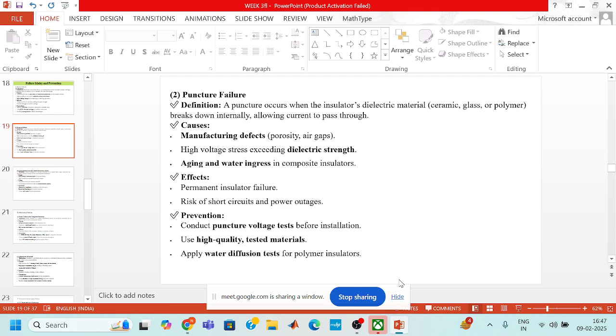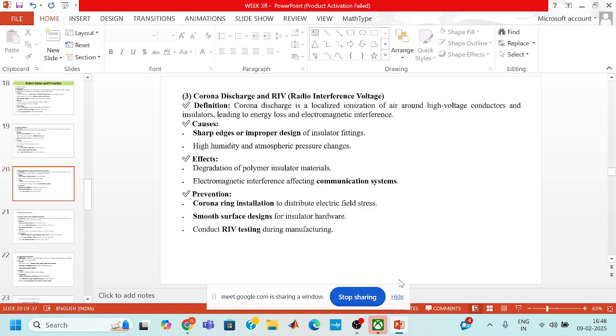Now, the B part is puncture failure. A puncture occurs when the insulator's dielectric material, like ceramic, glass, or polymer, breaks down internally, allowing current to pass through. The main cause of puncture failure is defects like porosity or air gaps introduced during the manufacturing process. High voltage stresses exceeding the dielectric strength, and aging and water ingress in composite insulators can also cause puncture failures. Puncture failures cause permanent damage to the insulators and risk of short circuit and power outages. So we can conduct the puncture voltage test before installation, use high quality tested materials, and also apply the water diffusion test for polymer insulators.